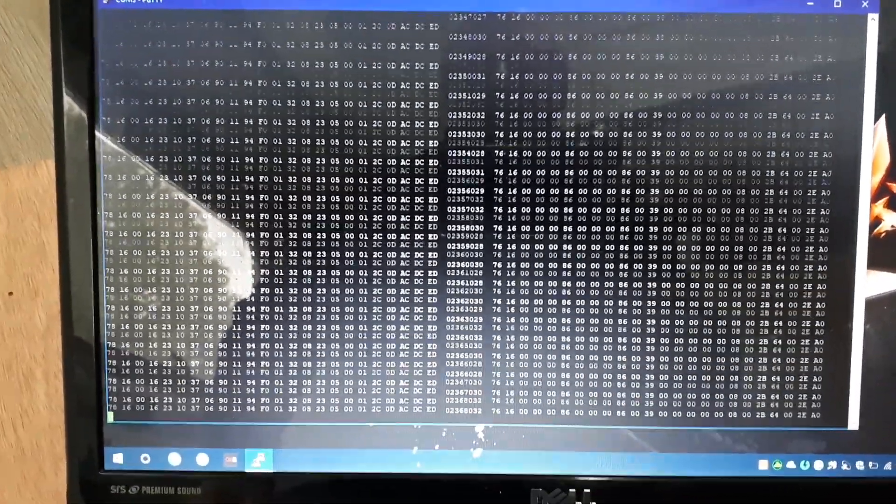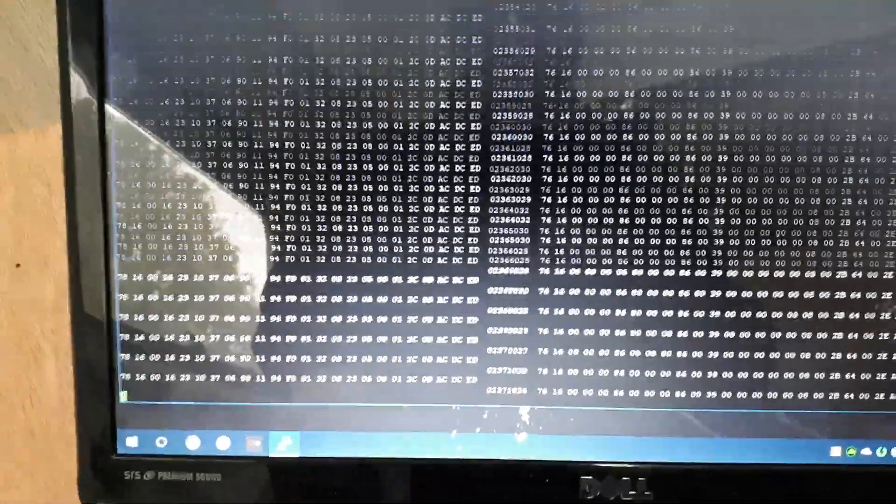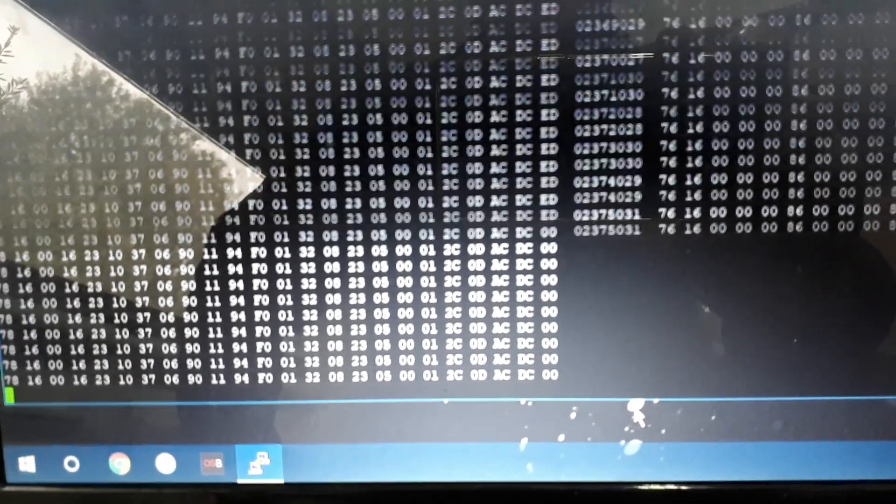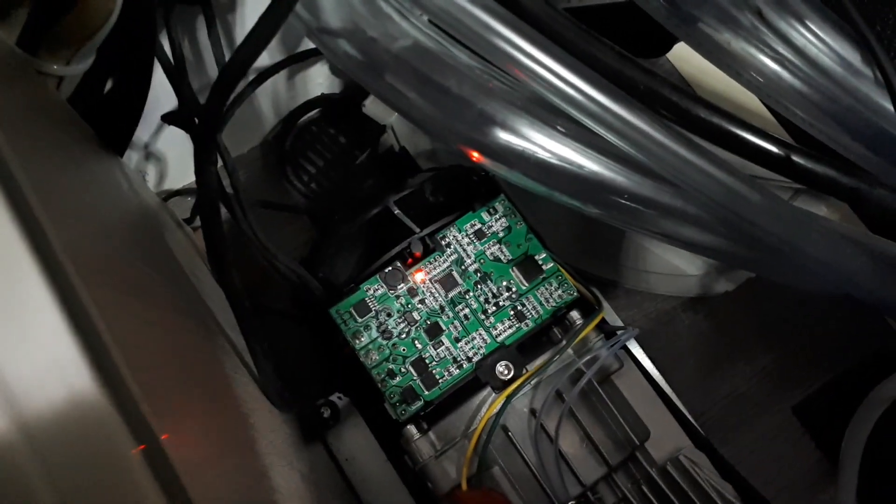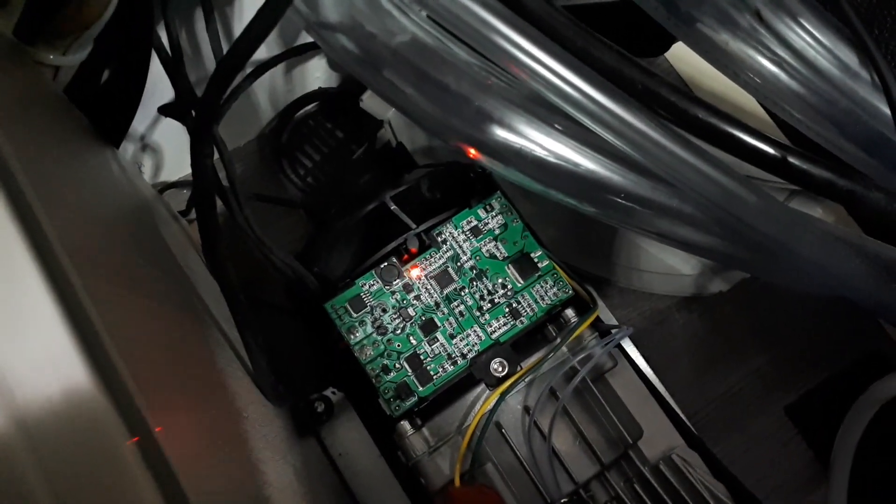In the heater there's no action at the moment, it's all turned off. I can actually generate an E07 fault by deliberately corrupting the CRC that's being sent. I can do that by typing C on the keyboard of the laptop. The very last byte now is the value of zero, which is a corrupted CRC. The heater unit is no longer happy, it's not responding with anything, and down in the heater we're getting an E07 code.